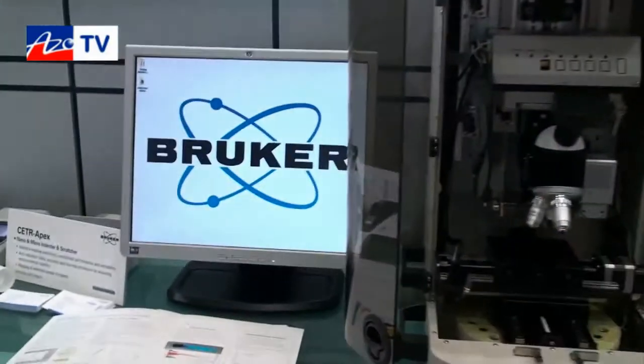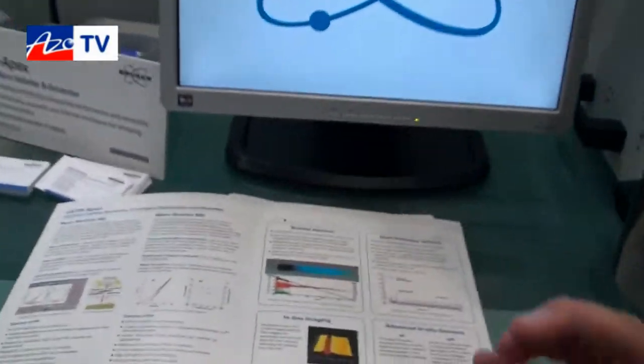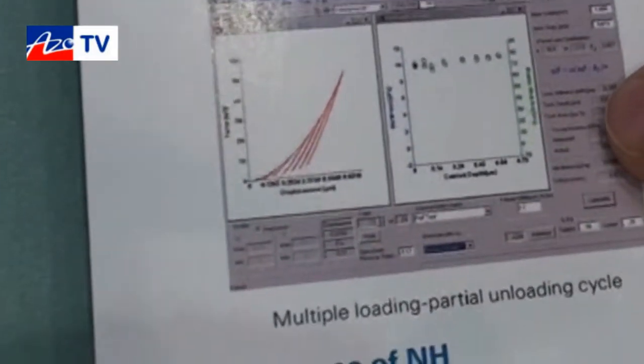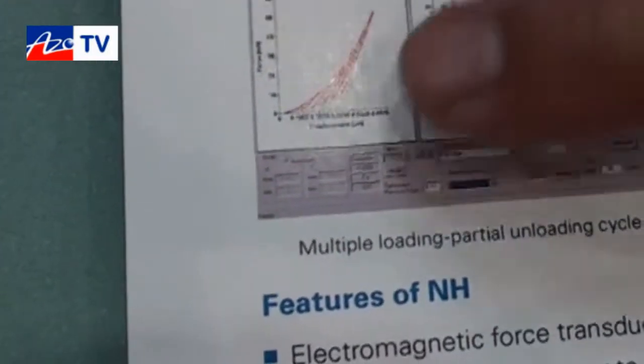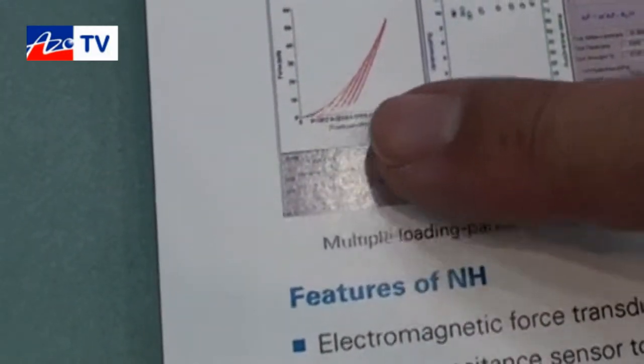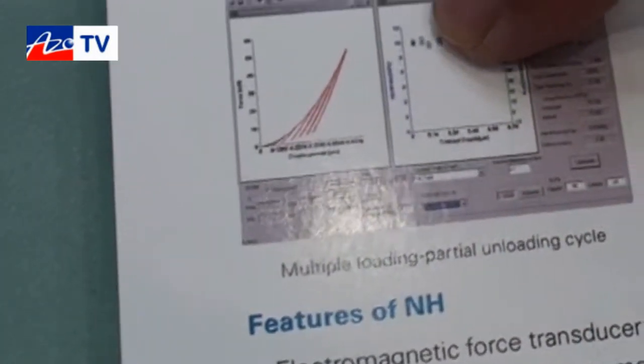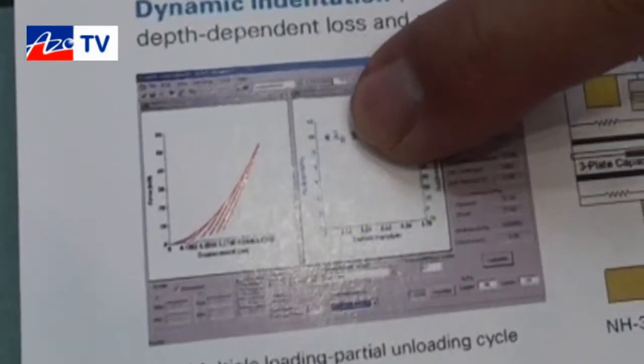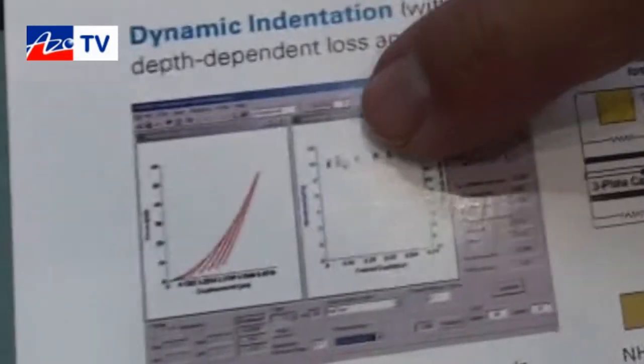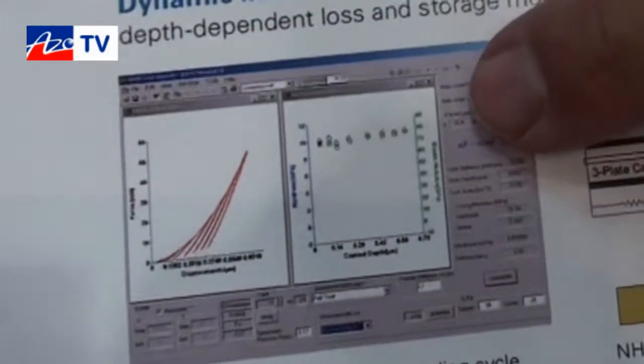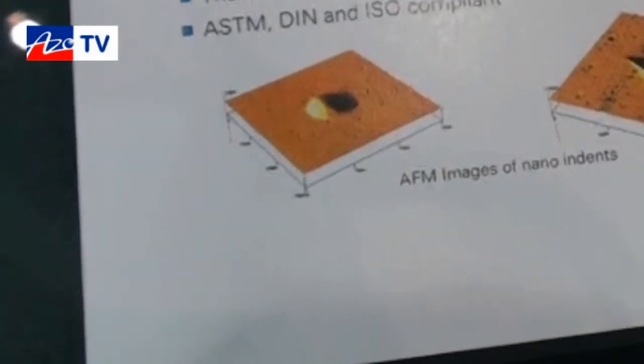With the software, once we do the indentation, the software creates a chart where you can see many indentations at different load levels. At each indentation level there is a marking where it produces the hardness and the Young's modulus at that indentation level for the material.